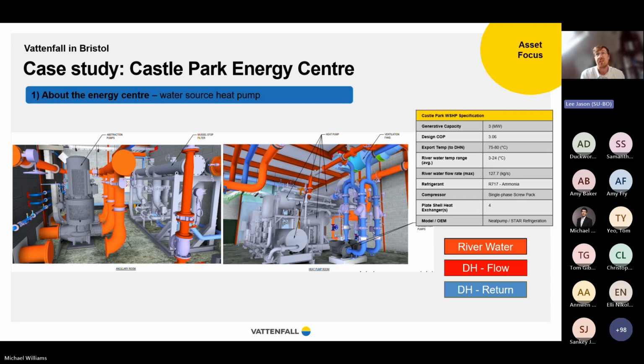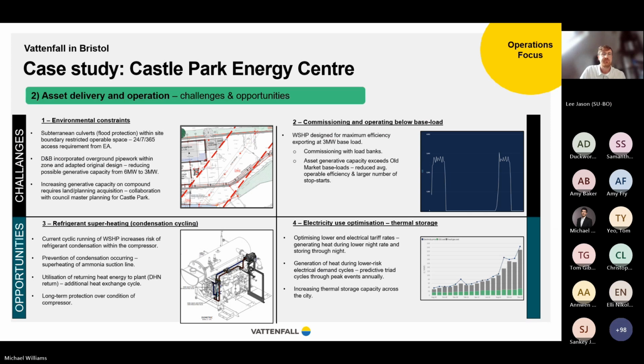What we see here essentially is just our flow coming into the top of the system before our return comes back out of the other. That flow water essentially travels through two sides of that, through 2 heat exchange sides of the actual heat pump itself, exchanging off of the oil that's used within the compressor to cool down that system, and then also on the actual ammonia itself to aid it turning back into a liquid state after it's gone through the compression cycle. So if you want to go to next slide, please.